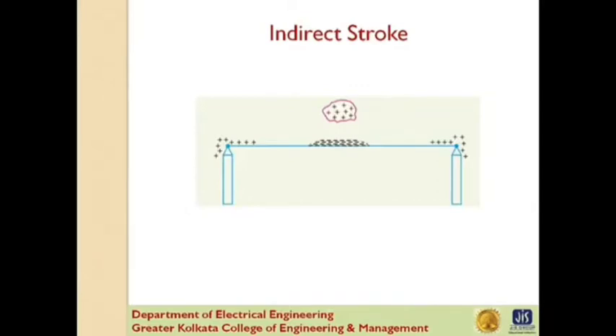Indirect stroke results from the electrostatic induced charge on the conductor due to the presence of a charged cloud. A positively charged cloud above the line induces a negative charge on the line by electrostatic induction. This negative charge will be only on that portion of the line directly under the cloud, and the portion of the line away from it will be positively charged. The induced positive charge leaks slowly to earth via the insulator. When the cloud discharges to earth or to another cloud, the negative charge on the wire is isolated as it cannot flow quickly to earth over the insulator. The result is that the negatively charged wave rushes along the line in both directions in the form of traveling waves. It is worthwhile to mention that the majority of surges in a transmission line are caused by indirect lightning strokes.